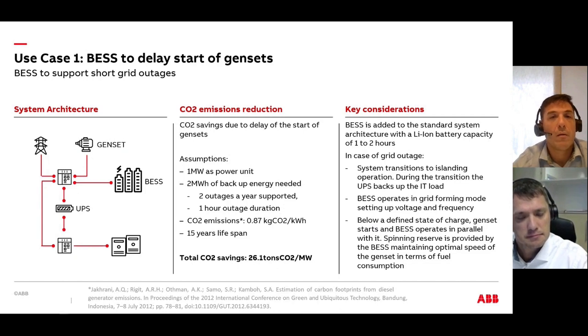Below a defined state of charge, which can be set up by the operator, the gensets are going to start and they are going to work in parallel with the BESS. But we need to consider that here the spinning reserve can be provided by the BESS. So we can maintain an optimal speed of the genset in terms of fuel consumption and CO2 emissions.